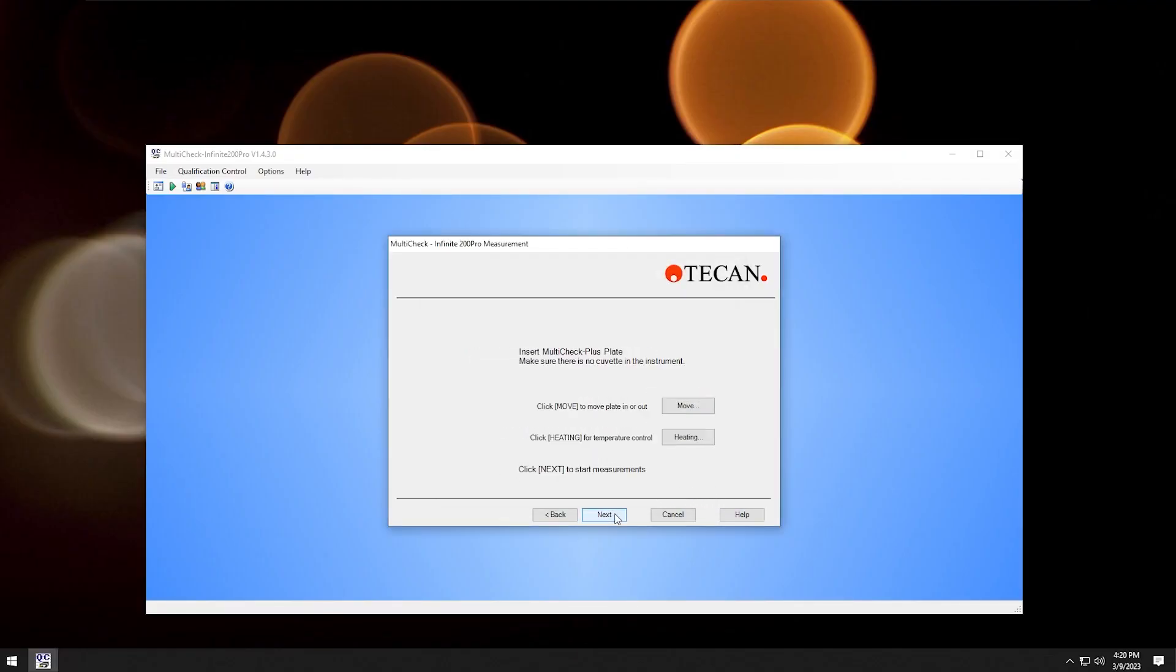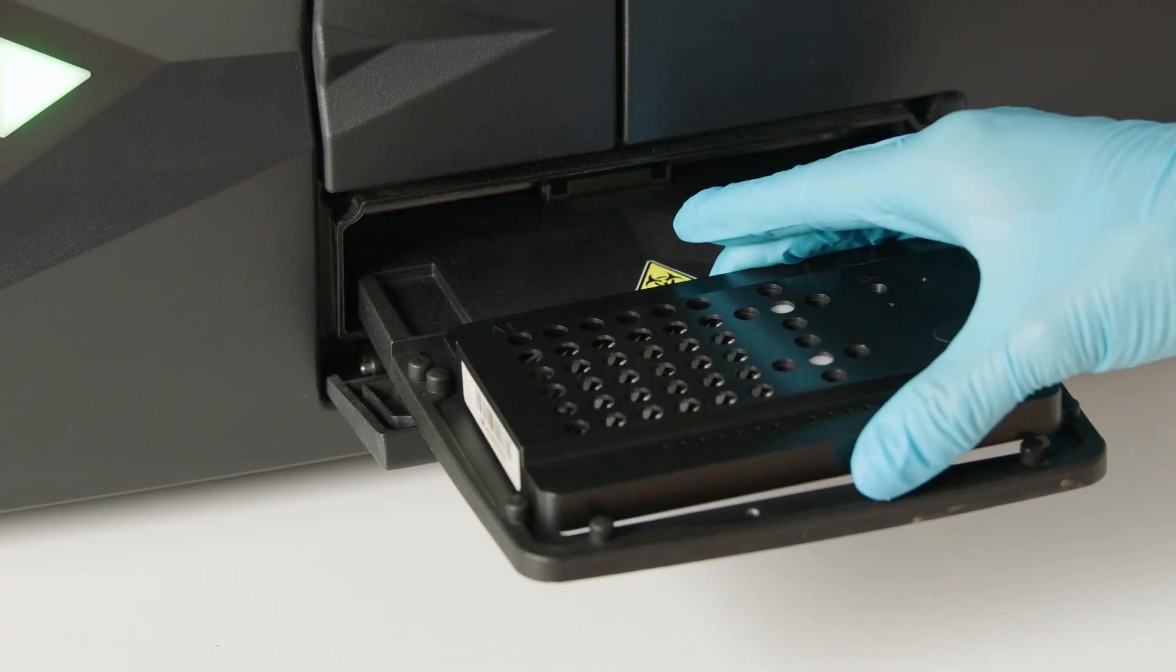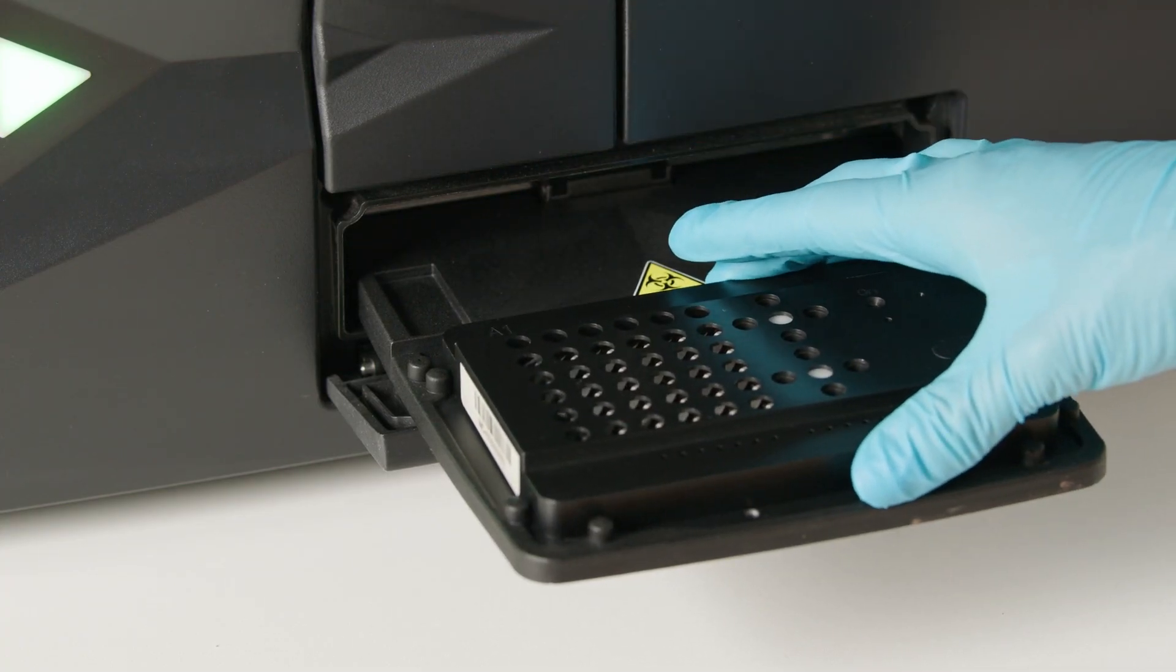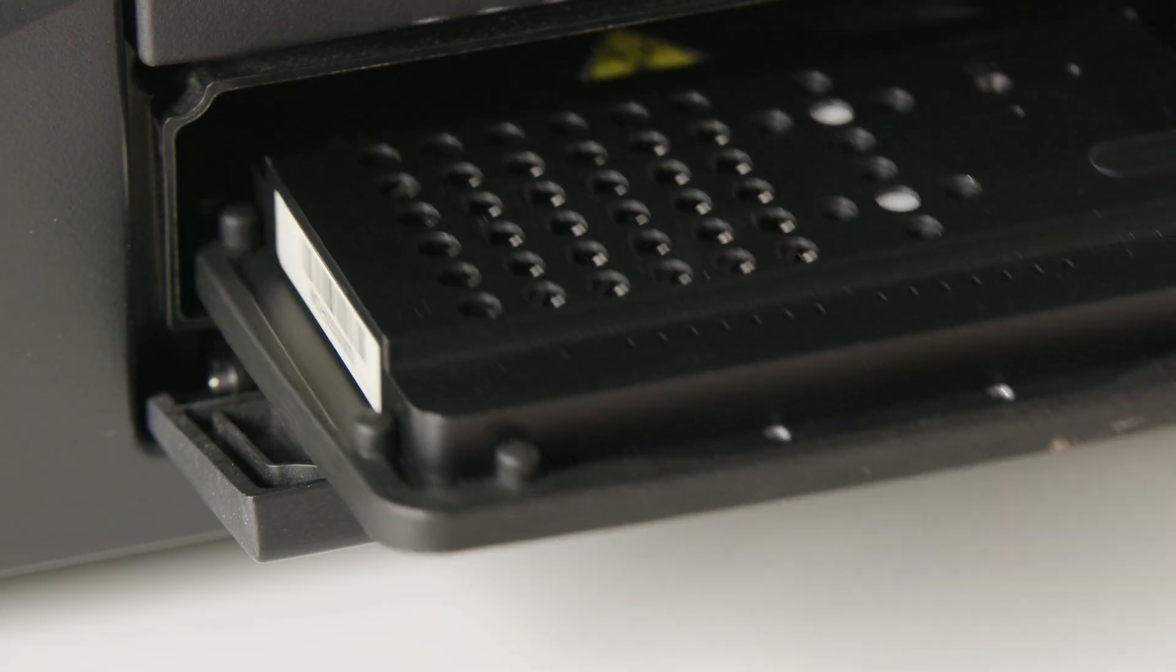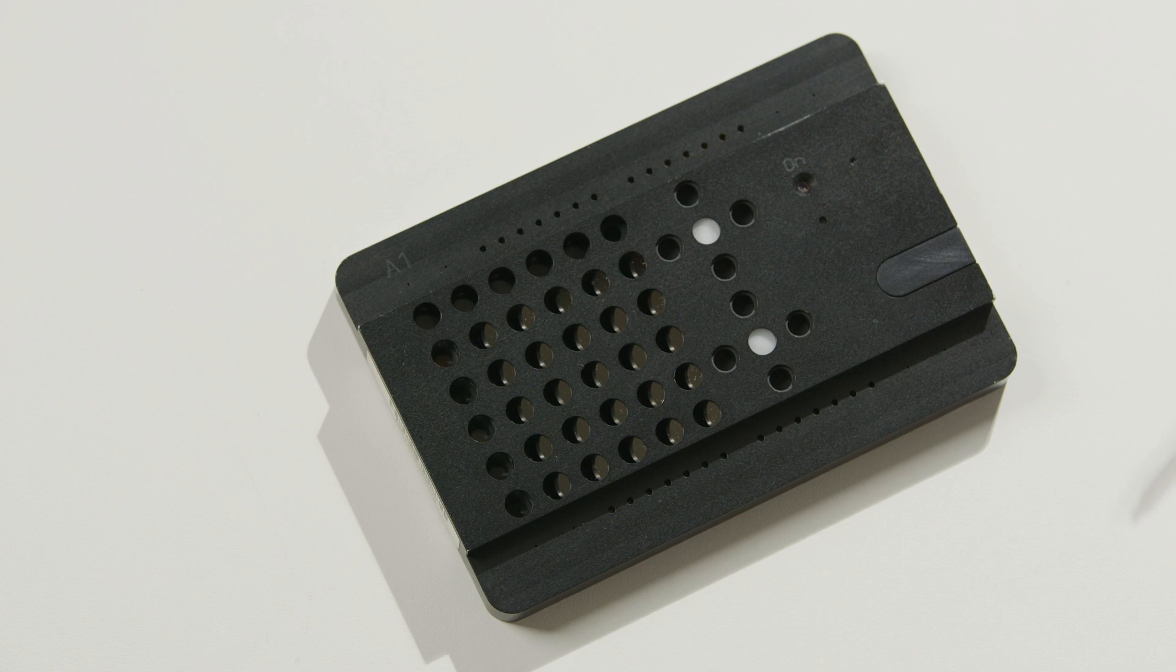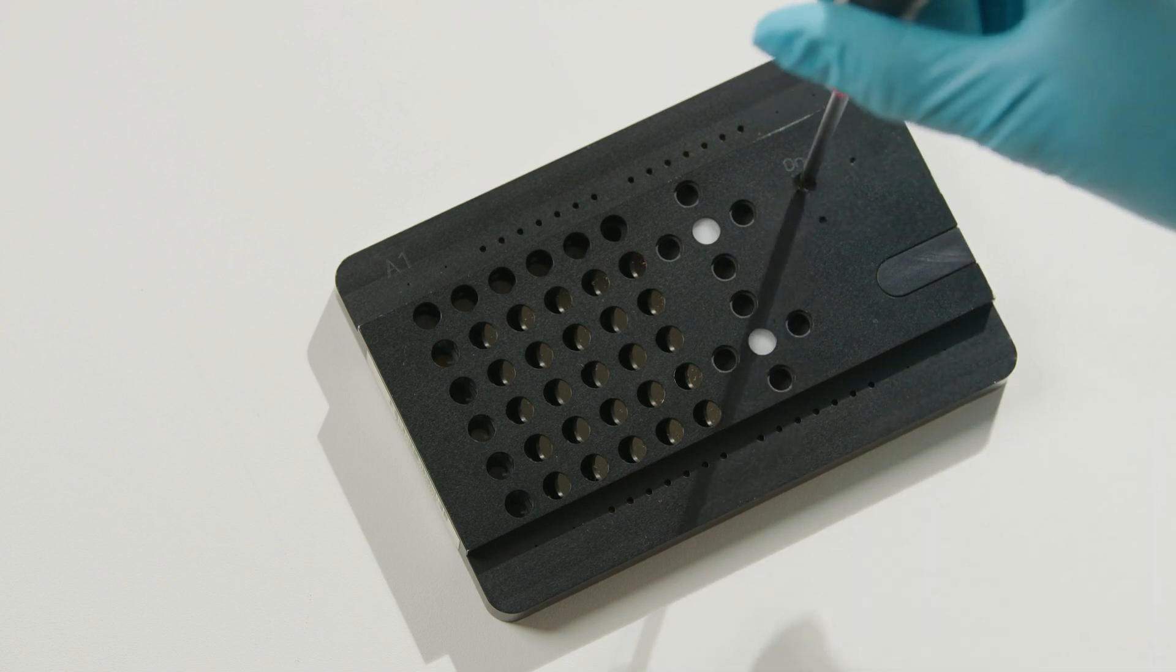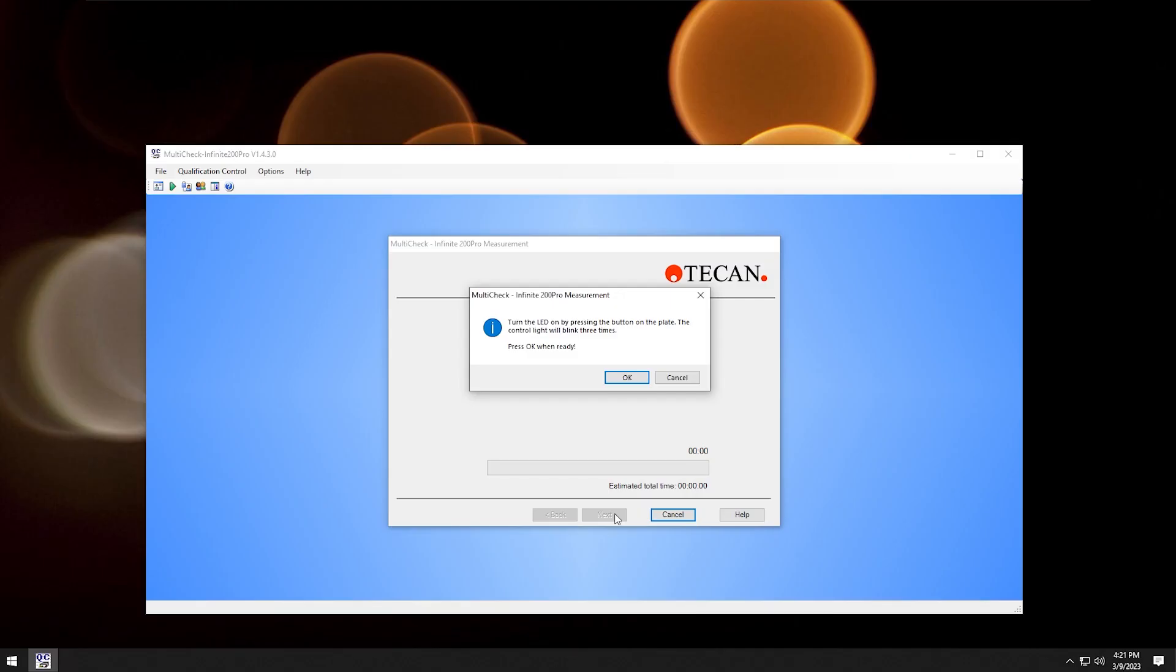We now have to insert the multicheck. Place the multicheck onto the plate transport. Make sure the A1 mark on the plate is in the top left corner of the transport holder. Back in the program, click next. If the luminescence is installed, click this button on the multicheck plate. Once the green light below blinks three times, click OK and the measurement starts running.